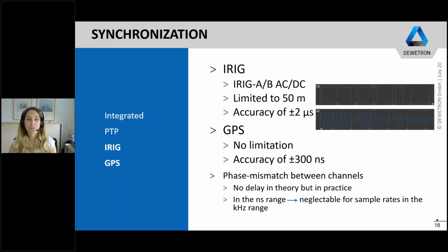It has an accuracy of 2 microseconds, and there are different IRIG signals. Here I mentioned IRIG A and B, but there are also other signals, and the letter refers to the pulses per second which are output. And then there's an AC or a DC signal, so you can have, for example, an IRIG B AC signal, which you would see in the second picture below, and in the first picture above, you see an IRIG B DC signal. So the AC signal has a sine wave as carrier signal, and the DC has a DC signal, of course.